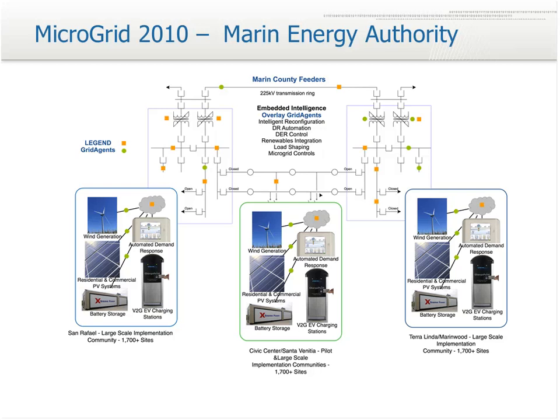you can integrate that. If you've got EVs charging on the system and you understand your PV production output and its variability, and you're hooked into the building control panel, you can reduce load to optimize charging or accommodate the variability on the solar side. You get a mini version of a microgrid—though a true microgrid is fully isolated from the network, requiring very quick balancing of supply and demand. Here it's more about optimized delivery: choosing the lowest carbon footprint, the lowest cost, or the highest amount of solar or renewable power going into the system.